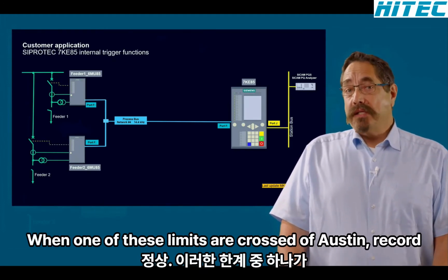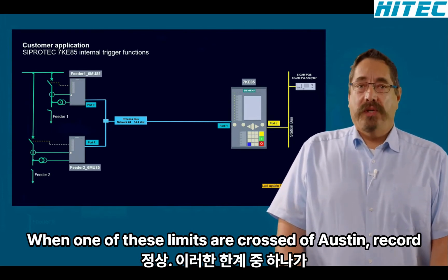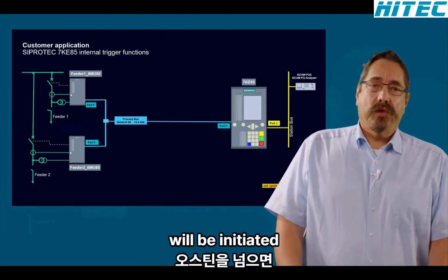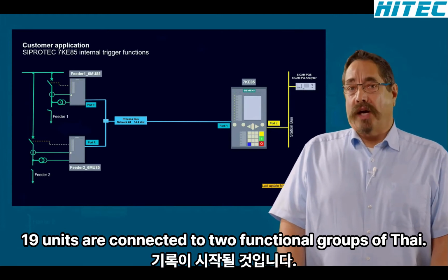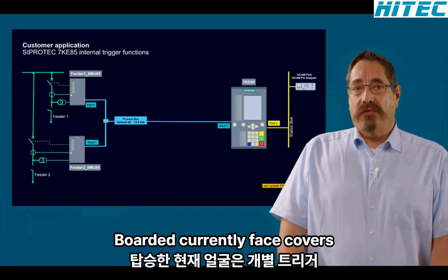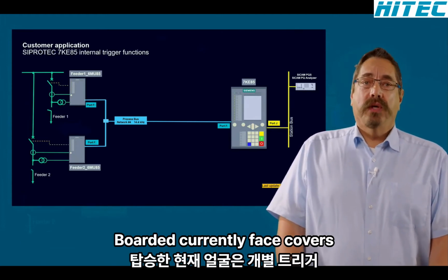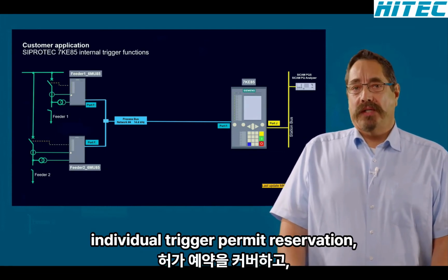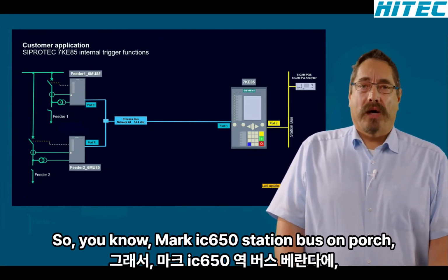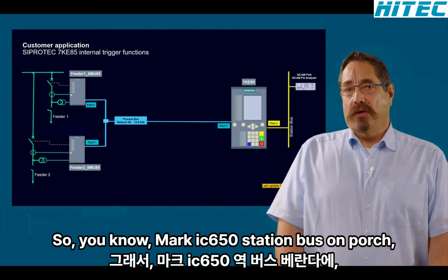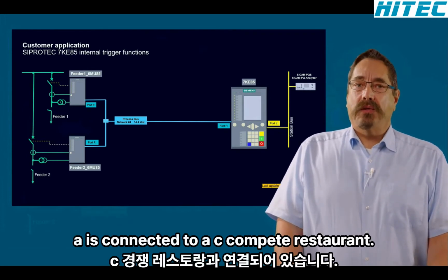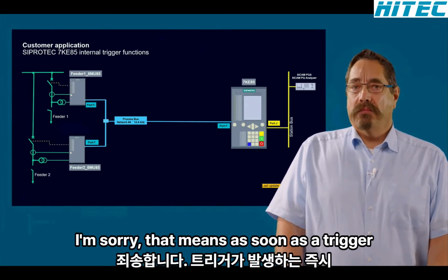When one of these limits is crossed, a fast-scan record will be initiated. The 2 merging units are connected to 2 function groups of type voltage current 3-phase. Each function group covers individual trigger parameterization. The yellow marked IEC 61850 station bus on port J is connected to a SICAM PQS runtime server.